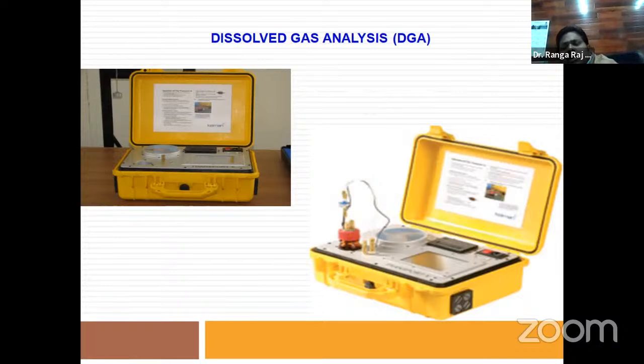Whatever gases are present in the oil, they release immediately into that free space, and those gases move to the gas measurement chamber. The gas detectors detect the various gases present in this bottle, and we can find their values through monitoring. This is a very costly and very sensitive test, but the output is very useful.